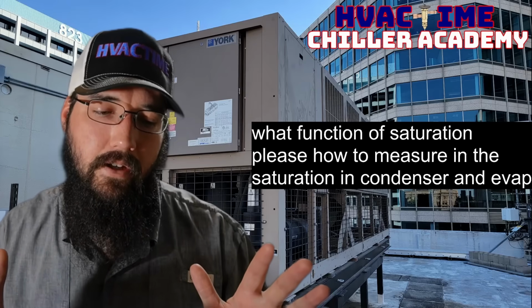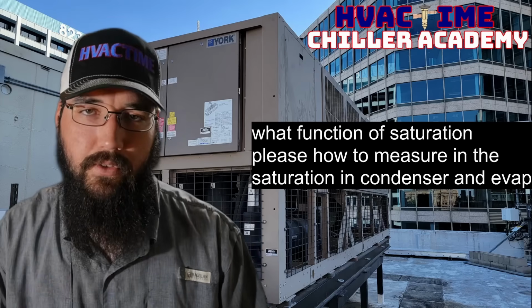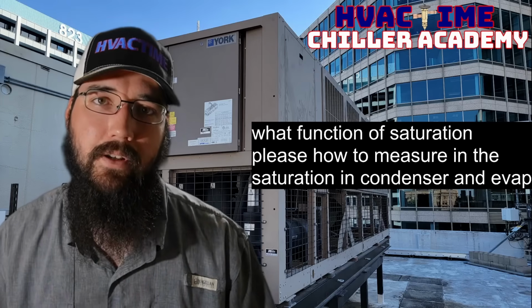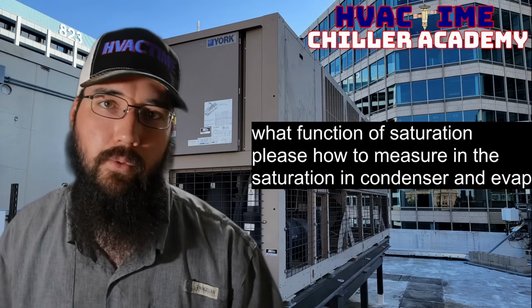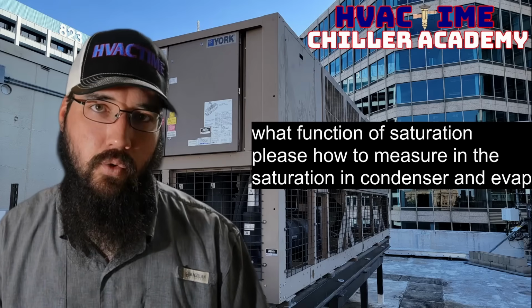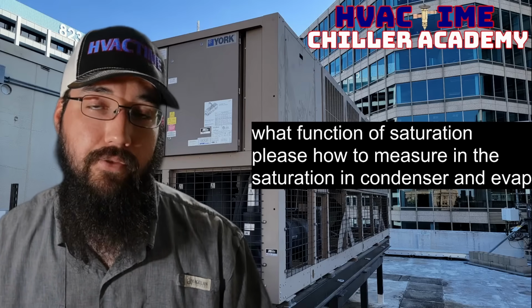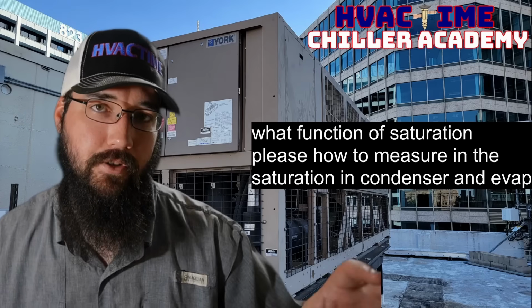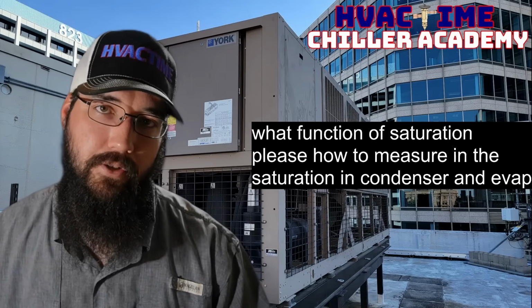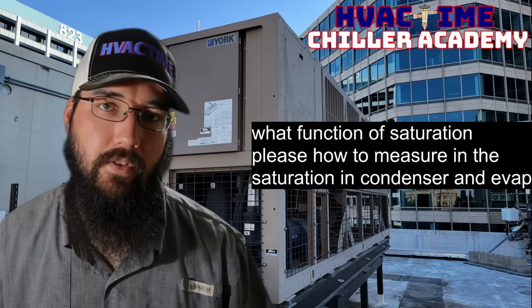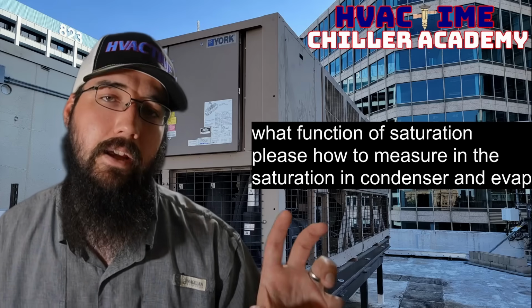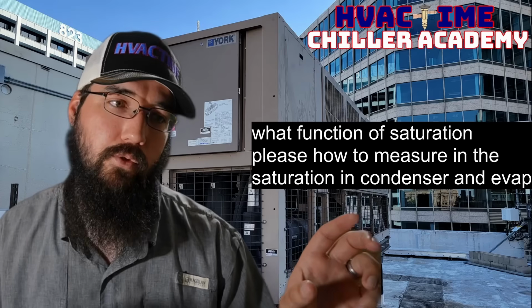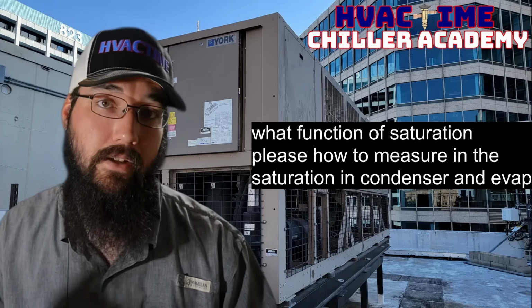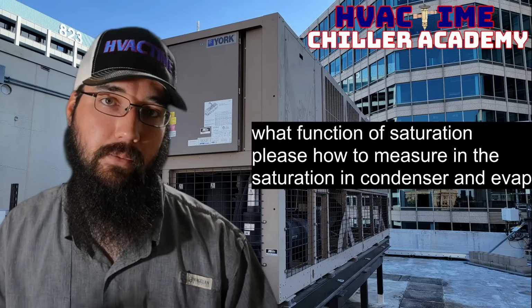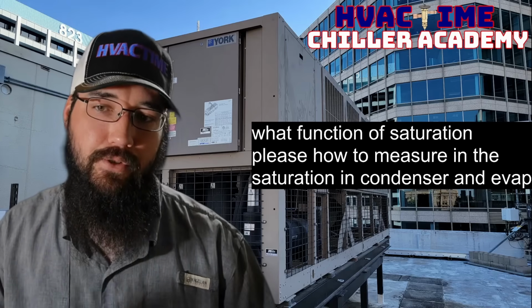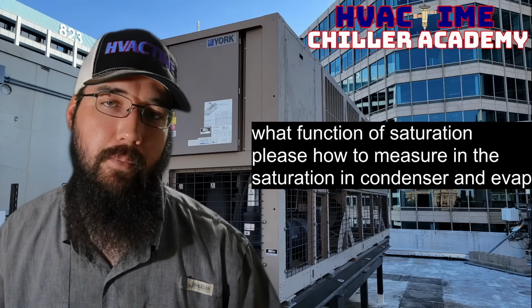You'll have to find, obviously you should know what your refrigerant is, what type it is. Is it 123, R11, R22, 134? Once you know what type it is, you can pull up a PT chart for that refrigerant. And that PT chart, pressure temperature chart, will allow you to take a pressure reading of the vessel. Let's say this was the evaporator, doesn't really matter. You take a pressure reading, and then you can use that chart to correlate that pressure to a set temperature, a saturation temperature specifically.